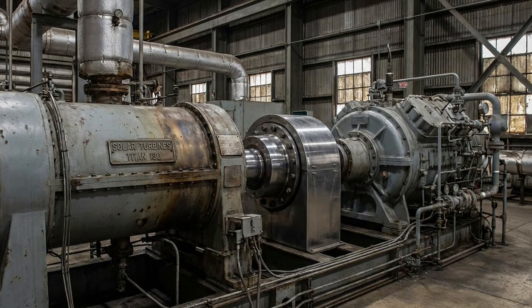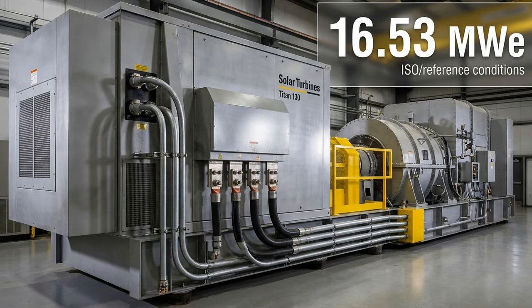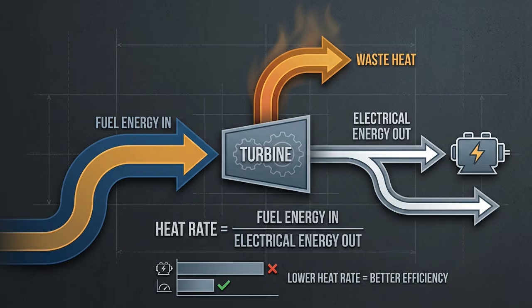In mechanical drive service, the Titan 130 is commonly published at approximately 17.5 megawatts, or about 23,470 horsepower, under reference conditions. For technicians, the important path is turbine output, coupling, and the driven compressor load. For generator set applications, the Titan 130 is commonly listed at approximately 16.53 megawatts electric under ISO or reference conditions. That value is not the same as mechanical drive output because generator losses and package configuration affect the delivered electrical rating. A published generator heat rate around 9,630 BTU per kilowatt hour describes how much fuel energy is required to produce electrical energy. Lower heat rate generally means better efficiency, but always compare values under the same rating assumptions.